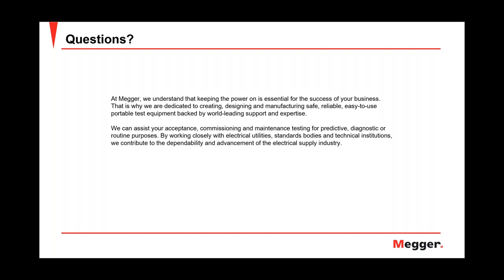All right, so that's a really good question that a lot of people actually have. So the short answer is not really. What that means is, if there is a very long cable run and then you have multiple transformers on that section, as Glenn was talking about in the presentation, some of that signal reflects back through all those splices and transformers. So you're losing some of the signal as it goes through. And the software has an auto detecting feature for the end of the cable run. Since you're stretching that signal out, you're not getting as high amplitude as you normally would to signal the end of the cable. So the software itself is having a hard time recognizing where the actual cable end is. And instead of just guessing and cutting off some of it, it's asking you as a user to determine where that end is.